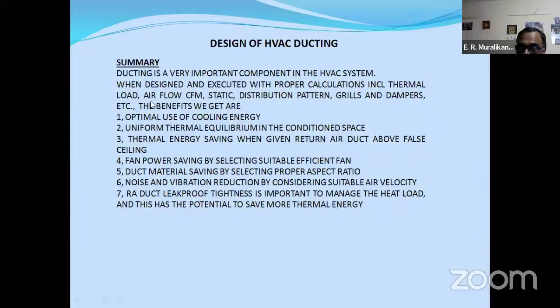Now, summary: ducting is an important component, and the design is executed with proper calculations including thermal load, airflow, CFM, static, distribution pattern, grills and dampers, etc. The benefits we get are optimal use of cooling energy, uniform thermal equilibrium in the conditioned space, thermal energy saving when giving a return air duct above the false ceiling, fan power saving by selecting a suitable fan, duct material saving by selecting proper aspect ratio, noise and vibration reduction by considering suitable air velocity, and RA duct leak-proof tightness is important to manage the heat load, and this has the potential to save more thermal energy.